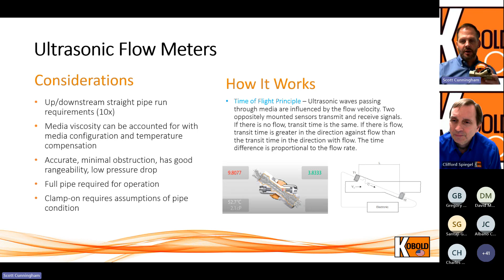Since your media is flowing in this direction, it's just like paddling from one dock to the other across a river. If there's no flow, the time it takes to get from here to there is the same as from there back. However, when you introduce flow, the faster the flow, the more impact it has on the time it takes to get from one sensor to the downstream sensor. So now you have a time differential, and that differential is directly proportional to the flow rate or velocity. Then, as mentioned, we calculate the flow rate based on the velocity of the fluid. That, in a nutshell, is how it works. Any questions on that?